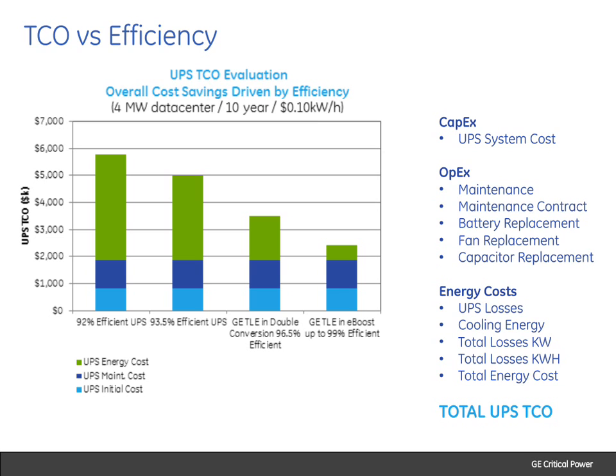One thing I didn't comment on here: what drives some of these differences in efficiency is a question we often get. If you look at the left-hand side, a 92% efficient UPS, this is a traditional efficiency of a transformer-based UPS, typically with input transformers, output transformers, what we call 2-level IGBT technology, which was fairly common 10 years ago.